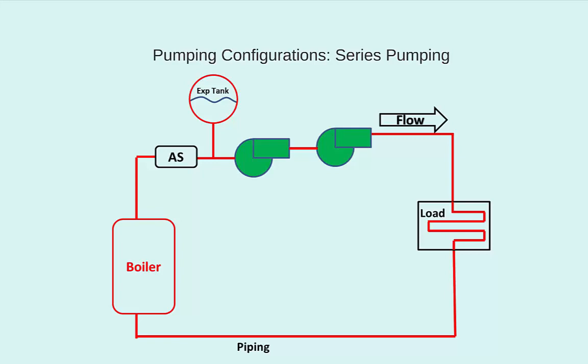First off, we could add them in series with each other. I have never encountered an HVAC hydronic system which actually utilizes such an arrangement. Issues occur if one pump is sized for higher flow rate than the other, in which case the forcing of the fluid through the smaller pump quicker than it can handle it can be very damaging to that pump. Cavitation can occur in the smaller pump, and there may be actually a chance to have a pressure drop across the smaller pump, not the intended pressure increase.